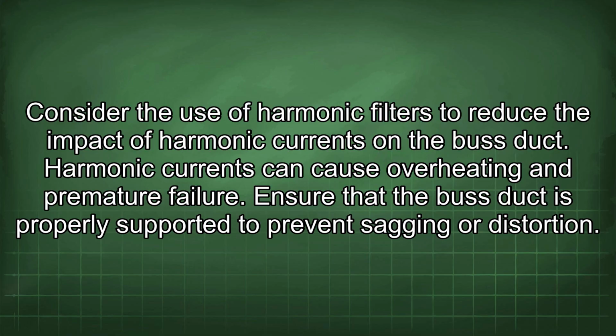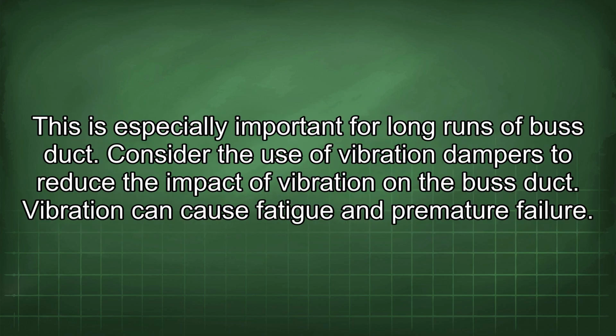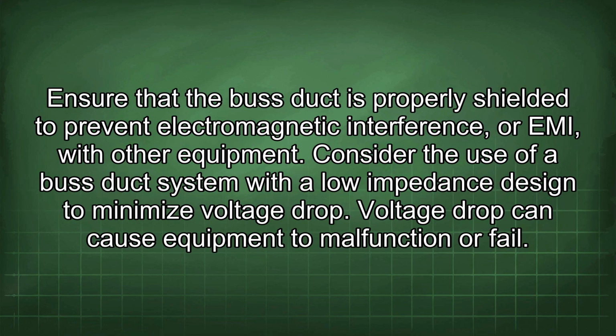Ensure that the bus duct is properly supported to prevent sagging or distortion. This is especially important for long runs of bus duct. Consider the use of vibration dampers to reduce the impact of vibration on the bus duct. Vibration can cause fatigue and premature failure. Ensure that the bus duct is properly shielded to prevent electromagnetic interference, or EMI, with other equipment.